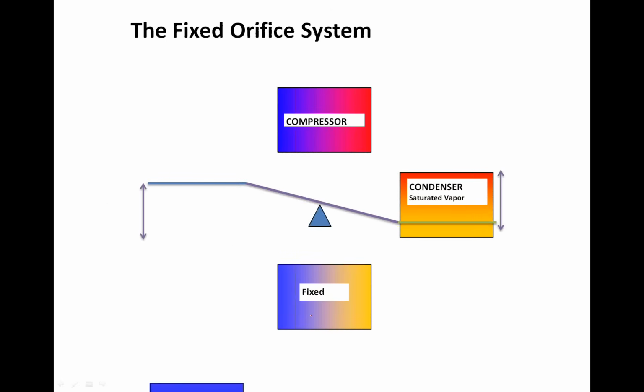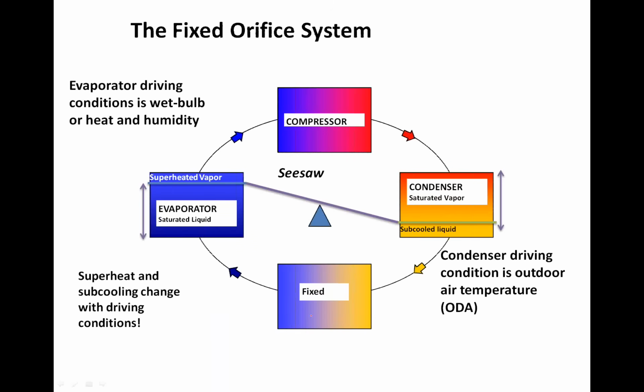When you look at a fixed orifice system, I always call these seesaw systems, because of what happens here. Let's just think about what happens on our condenser side. A fixed orifice system is simply a hole. It has no way of opening or closing or changing the size of that hole. So simply if we drive the pressure up on the condenser, and that's what we're doing on this side of the system on the right-hand side here, you can see where my arrow's at.